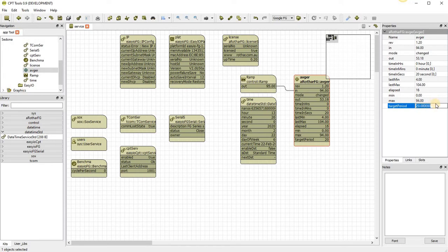Change. So at 30 seconds past, it will execute its average calculation for the 30 seconds. It will always try to line up with the minute boundary. If you're recording every 5 minutes, it will line up with the hour boundary. If you're recording every 4 hours, it will line up with midnight.